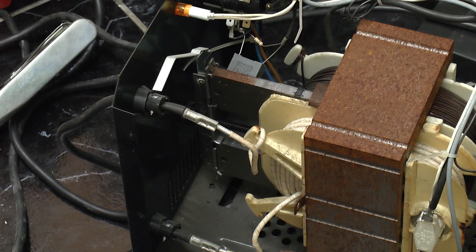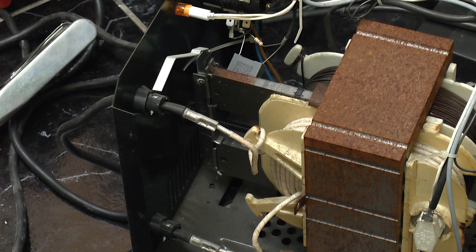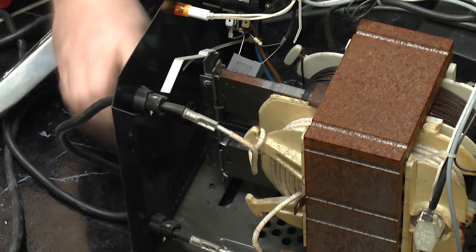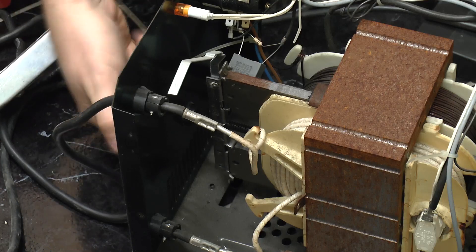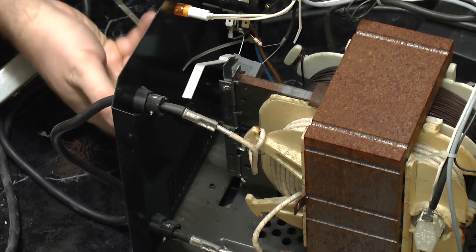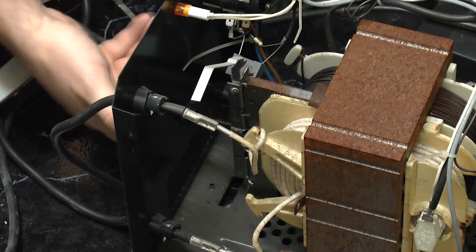The two laminated steel bars sticking out of the side of the transformer are what control the welding current. At the moment they're fully retracted out of the transformer and it's running at maximum current. If I turn the hand wheel it drives them further into the transformer and that is what turns the maximum welding current down.